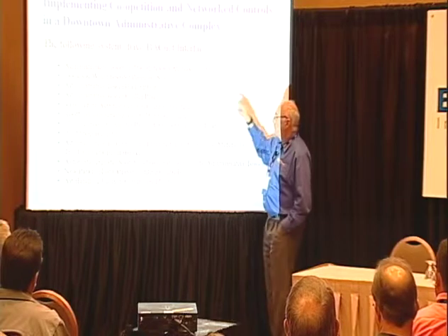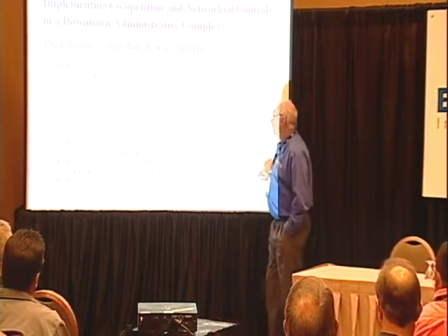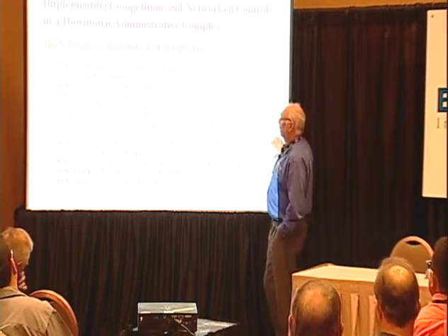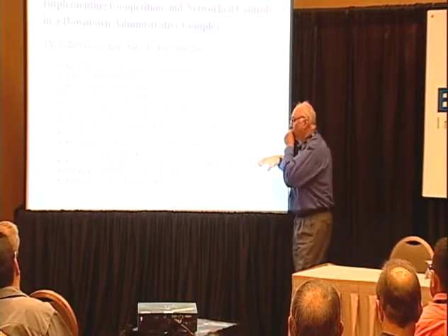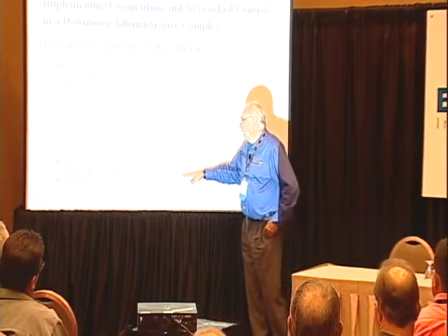Chiller plants had to be replaced, fire alarm upgrades, some rooftop units, an IT server room and a UPS, a humidifier for the print shop. The electric, they had to put in a whole electric plant for the new chiller plant, transfer switches. It's a facility that requires generator power, parking lot lighting, and some air handling units. Each one of these projects was done separately, and different vendors were involved in doing the controls, and different vendors were involved in supplying the equipment.